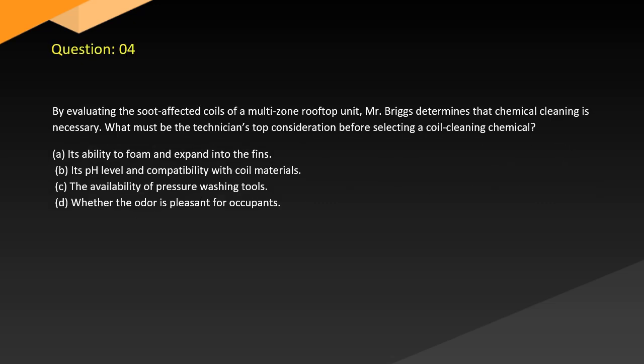Question 4. By evaluating the soot-affected coils of a multi-zone rooftop unit, Mr. Briggs determines that chemical cleaning is necessary. What must be the technician's top consideration before selecting a coil cleaning chemical? A. Its ability to foam and expand into the fins. B. Its pH level and compatibility with coil materials. C. The availability of pressure washing tools. D. Whether the odor is pleasant for occupants.